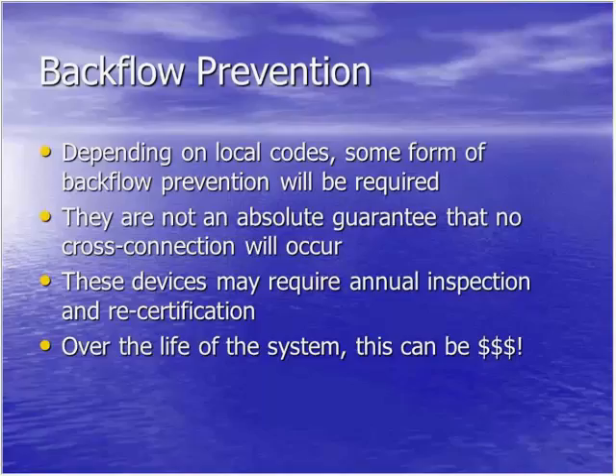So the user, whether it be a homeowner or a building owner, having somebody come in on an annual basis to check it out adds to the bottom line. And just to clarify, if you have a potable water connection to your heating system, you have to have some means of backflow prevention. So by using a package feeder, you eliminate the need for that expensive annual maintenance of the backflow prevention device. Correct.